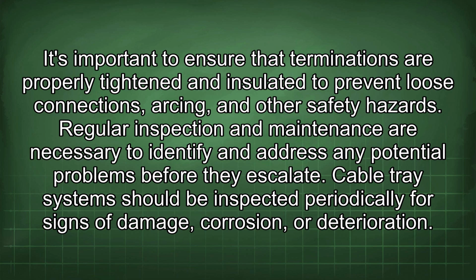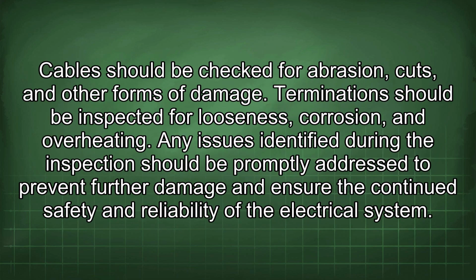Regular inspection and maintenance are necessary to identify and address any potential problems before they escalate. Cable tray systems should be inspected periodically for signs of damage, corrosion, or deterioration. Cables should be checked for abrasion, cuts, and other forms of damage. Terminations should be inspected for looseness, corrosion, and overheating. Any issues identified during the inspection should be promptly addressed to prevent further damage and ensure the continued safety and reliability of the electrical system.